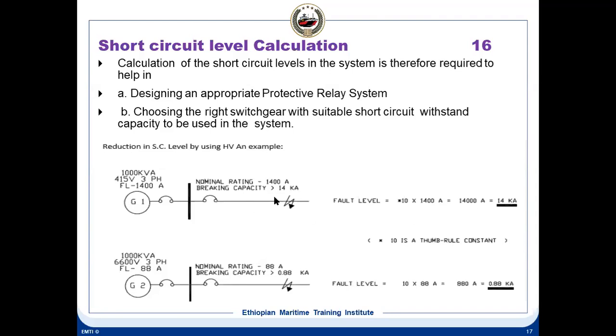This breaker has to be rated for 14,000 amps. Whereas in this case, it is 6,600 volt, but full load current is 88. So if you multiply this with 10, that's the fault level current, it becomes 880 amps. So the breaker capacity needs to be only 0.88 kA, that is 880 amps only. So you can see here the difference between this breaker capacity and this one is drastically reduced because of stepping up the voltage from 415 volt to 6600 volt. So another advantage is the short circuit level is drastically reduced. Here it is 14,000 amps. Here now we are reduced to 880 amps.